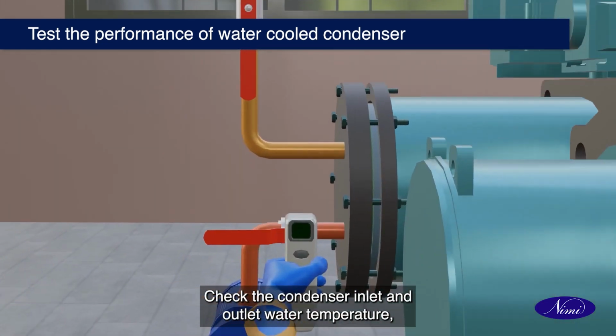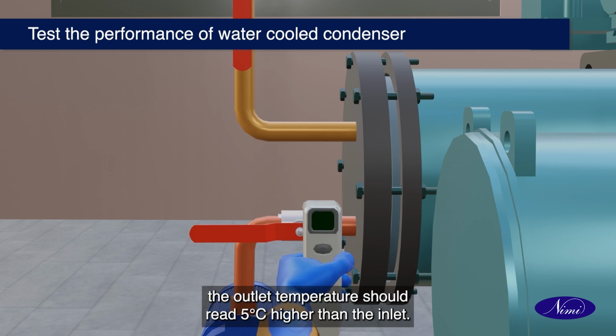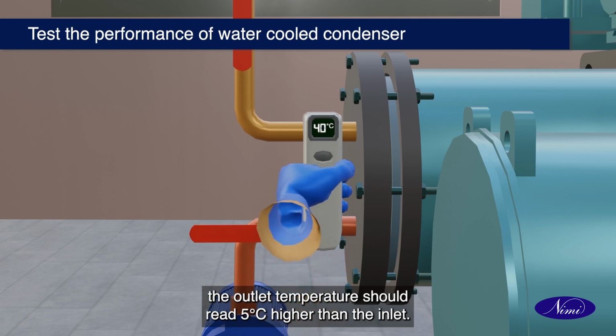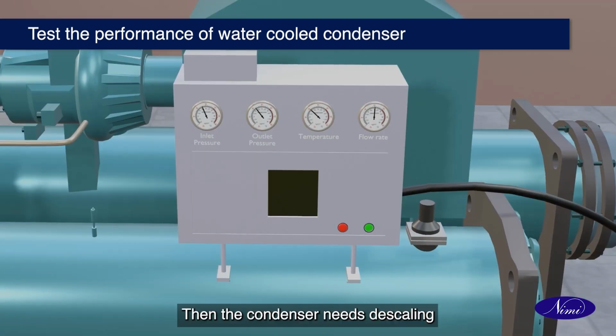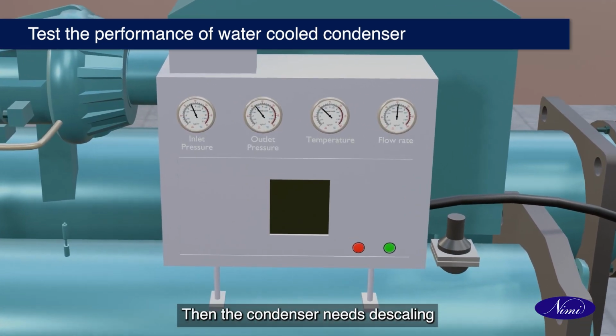Check the condenser inlet and outlet water temperature. The outlet temperature should read 5 degrees higher than the inlet. If it reads lesser, then the condenser needs descaling.